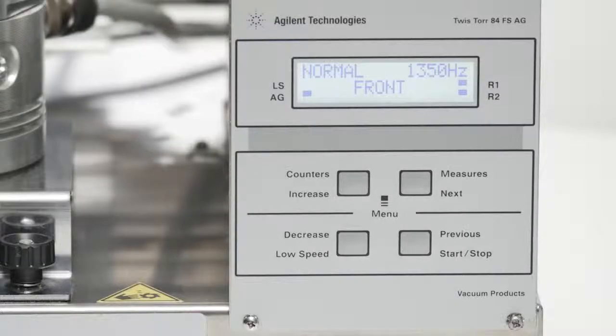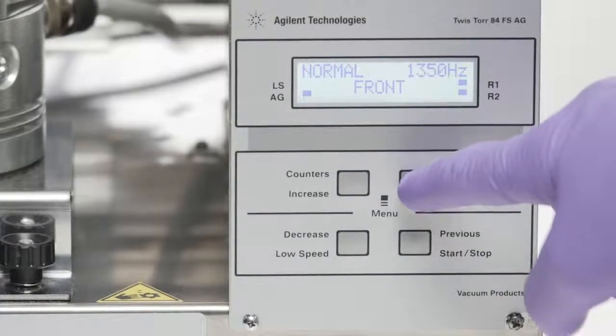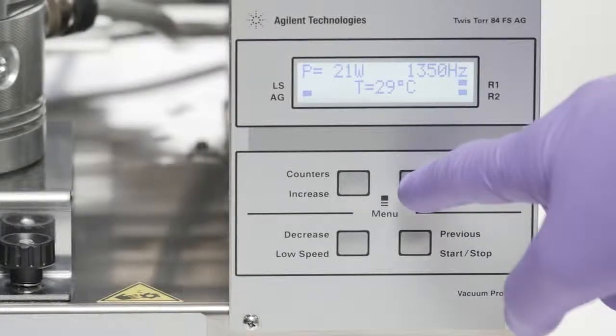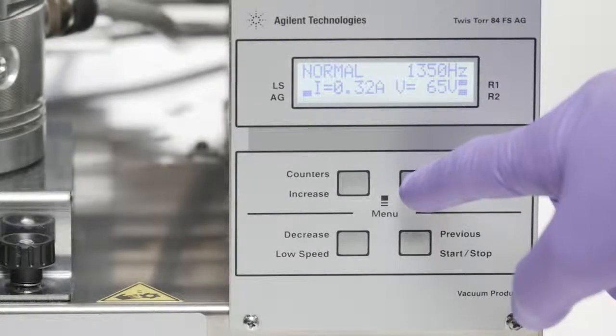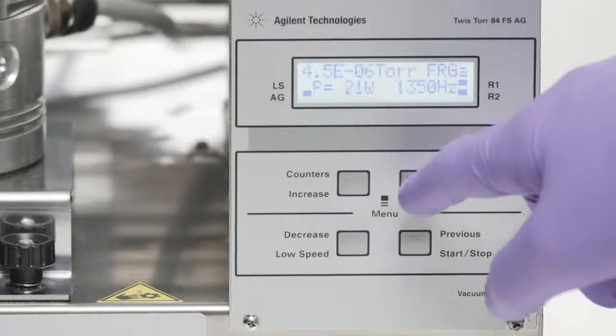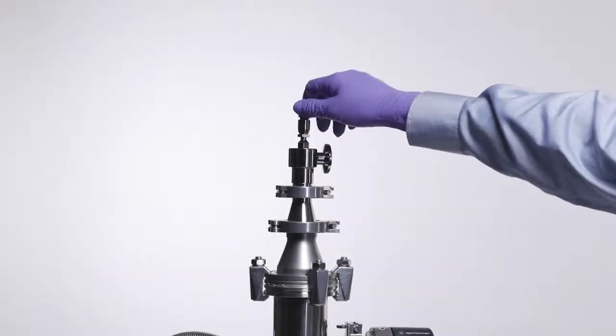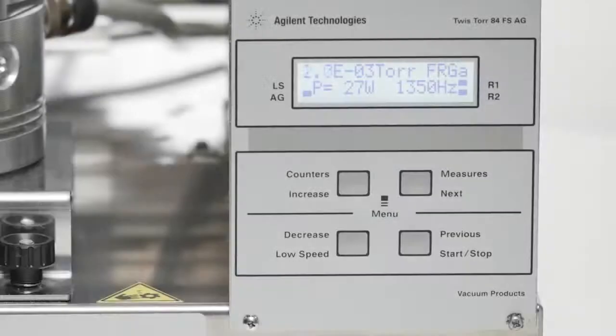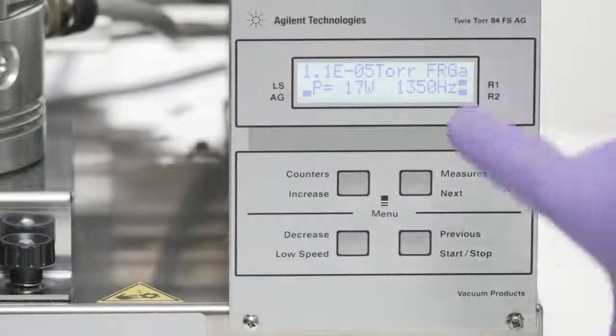With our turbo pump operating at full speed and in normal conditions without a gas load, we can see that the parameters look very typical. As we introduce a gas load, we notice a rise in pressure and power. As gas load decreases, we watch the controller recover back to normal operation.